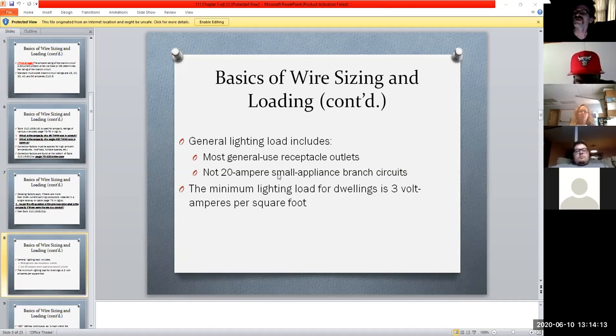But yeah, we'll get into what lighting loads are. They're typically the easiest. Lighting loads don't usually change on the fly. We can go ahead and make branch circuits off lighting loads. Very typically, we're just delivering with 15 amp breakers to given lighting branch circuits. Usually nothing over 20 amps. It really depends though. Sometimes there are certain situations where they might have some special luminaire installed that's got some crazy wattage to it, but that would be something to be considered from the plans. Usually you can plan it out, and because it's low load, the light bulb doesn't burn that much, so usually we can lump a few different lighting branch circuits together and have them all traveling off of one circuit breaker, if you will.